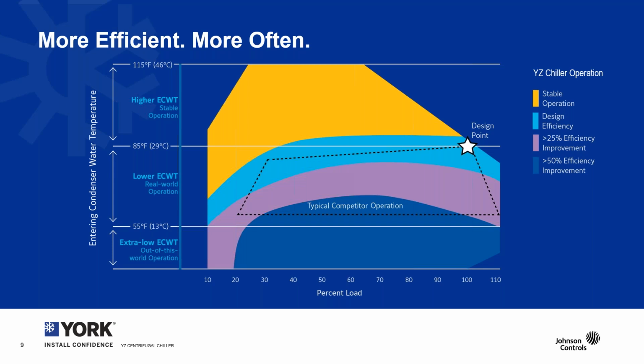And the dotted line represents the typical range of chillers available in the market in terms of an operating map. And the YZ, like the YMC squared and similar to the YK, offers a much broader operating map to customers, which gives you both added reliability, but also added performance. The top side of that graph represents maybe a dirty cooling tower or a failure of a component in the condenser water system, something that's unexpected but forcing you to operate in a condition that is on the high end of the operating map for a chiller. And our operating map will let you run reliably and maintain cooling.